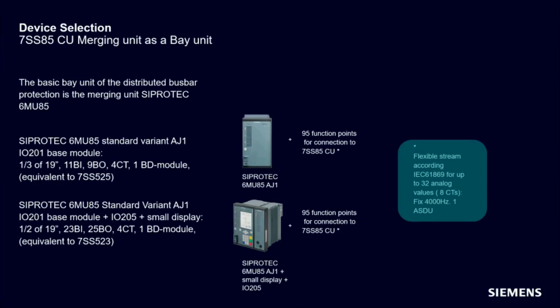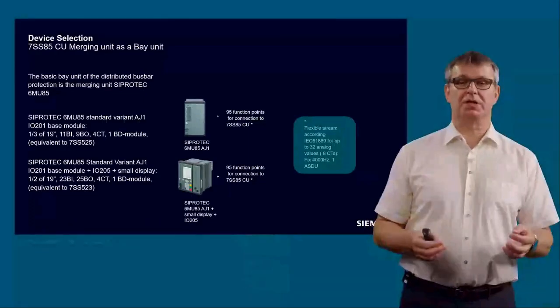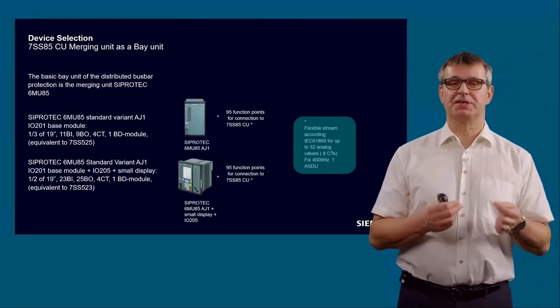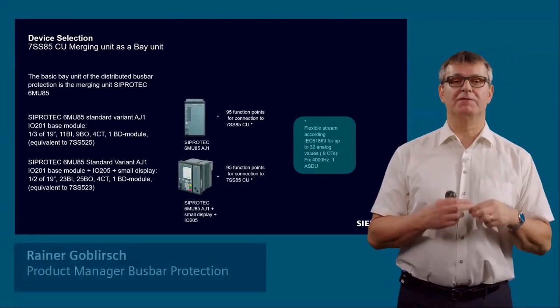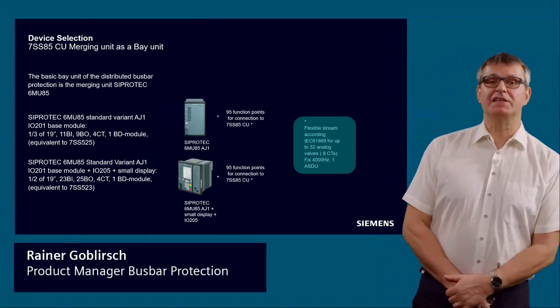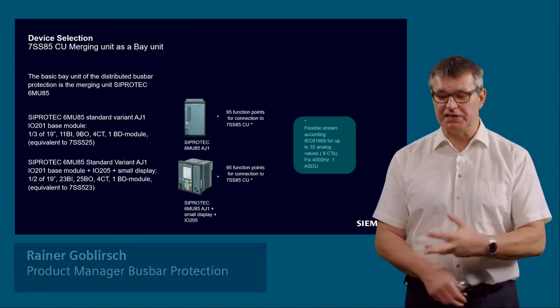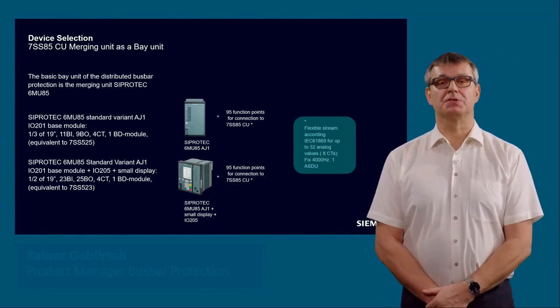Of course, you have to think about adding more I/O modules to cover all these 8 CTs, but in principle it's possible, and you have to pay this additional 95 function points only one time. With these additional 95 function points, you can send up to 8 current measuring points to the 7SS85 central unit.